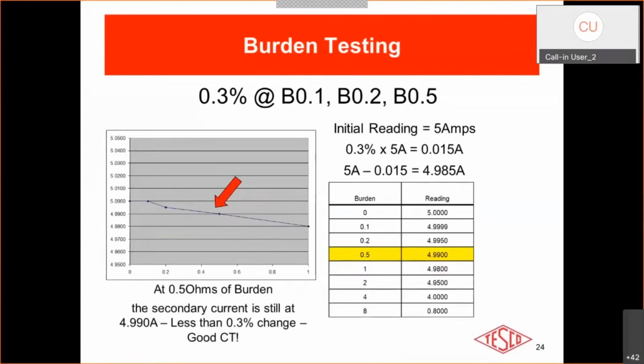Zooming in here, we can see from the spec up here that we're looking for no more than a 0.3% drop up to 0.5 ohms of additional burden applied. So as you can see here at the 0.5 test point, we still have 4.99 amps of current, and therefore the secondary current change is less than 0.3%, and therefore you have a good CT.